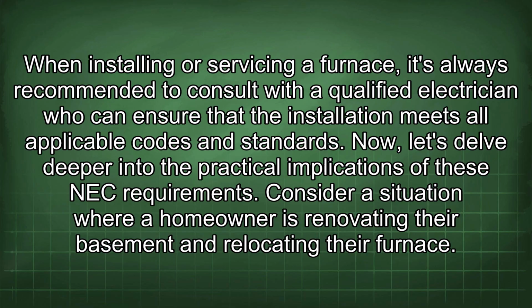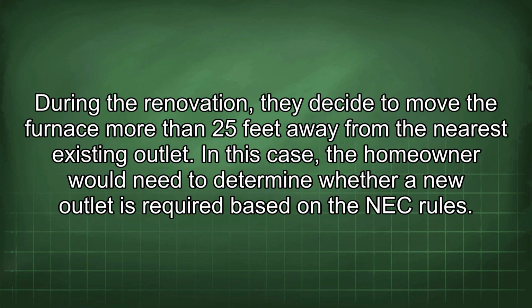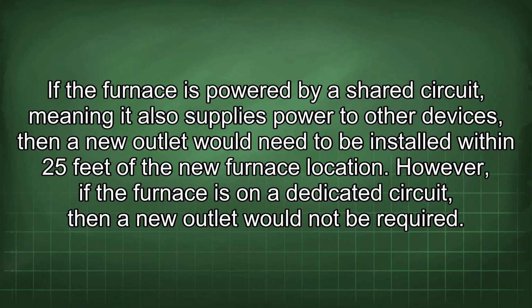Now let's delve deeper into the practical implications of these NEC requirements. Consider a situation where a homeowner is renovating their basement and relocating their furnace. During the renovation, they decide to move the furnace more than 25 feet away from the nearest existing outlet. In this case, the homeowner would need to determine whether a new outlet is required based on the NEC rules. If the furnace is powered by a shared circuit, meaning it also supplies power to other devices, then a new outlet would need to be installed within 25 feet of the new furnace location. However, if the furnace is on a dedicated circuit, then a new outlet would not be required.